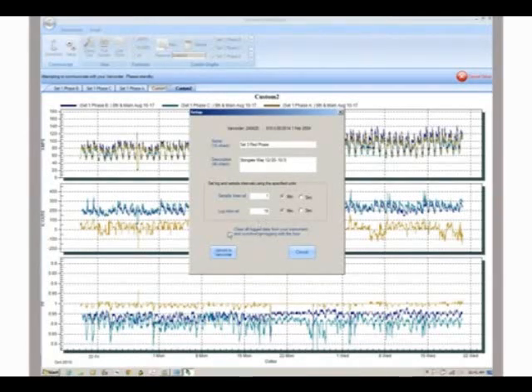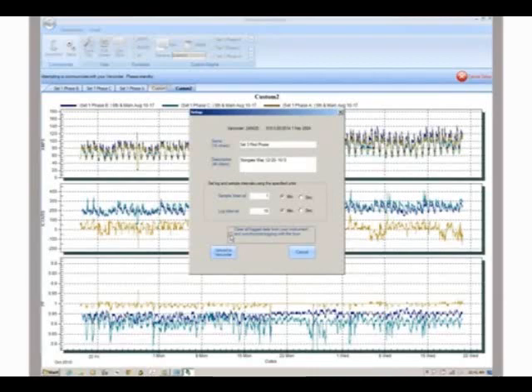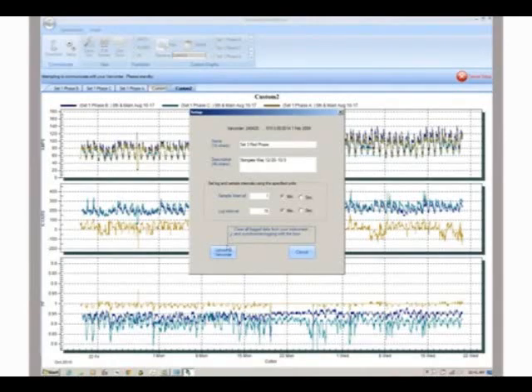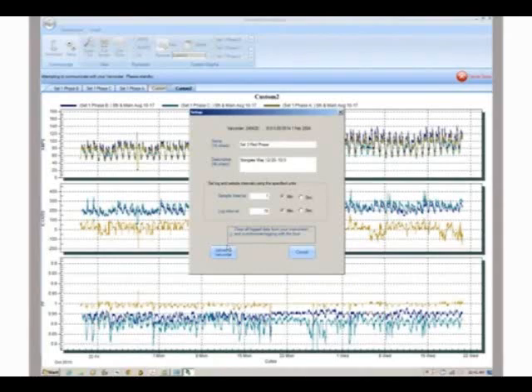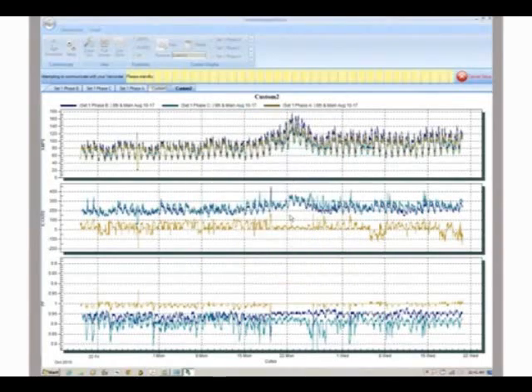By selecting the clear all data from your instrument and synchronizing with the hour, all previously recorded data will be erased and synchronized to the hour. When this is selected for all varcorders and they're set with the same log interval, they'll all record data at the same time. Once the upload button is clicked, the changes are saved, and your recorders are ready for redeployment.